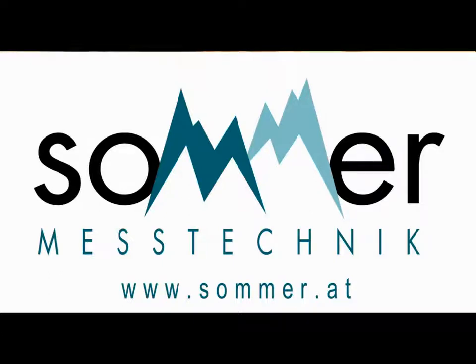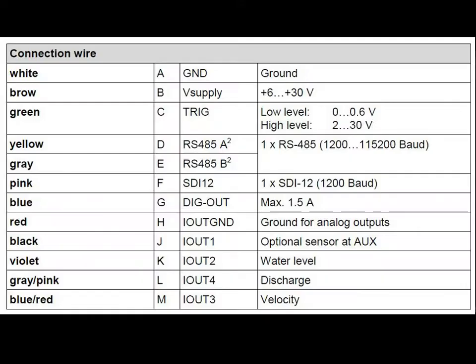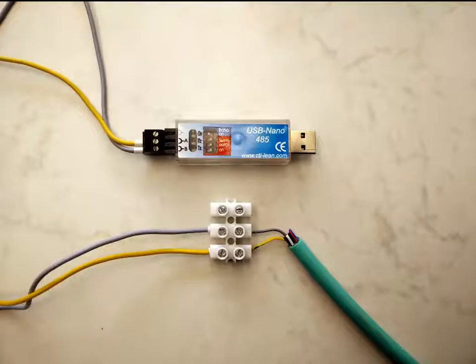My name is Matthias Kaufmann and I'd like to show you the parameterization of the RQ-30 radar discharge sensor. To connect to the RQ-30 you need an RS-485 adapter. On the standard cable which comes with the RQ-30, please connect the yellow cable to the A canal and the gray cable to the B canal of the RS-485 adapter. Please connect it to your laptop, to the USB port, and then open the RQ Commander Modelling.